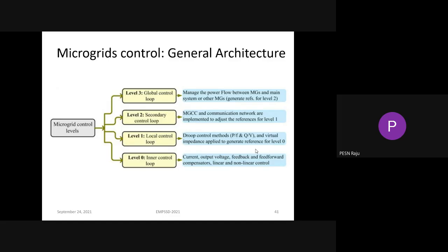In the secondary level, mainly the MGCC will communicate with the local control of all the DERs, and it will provide the reference to all the local control. In the global control, it mainly manages the multiple MGs, providing the communication among the multiple microgrids, and also it provides the reference signals to the other microgrids based on the reference signals getting from the utility, power system utility.